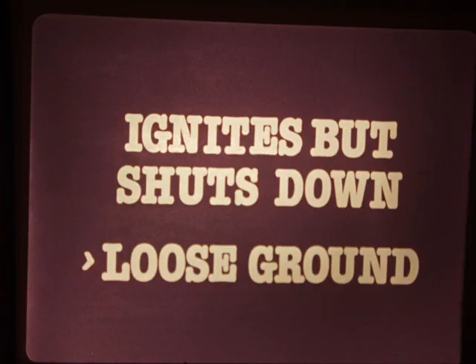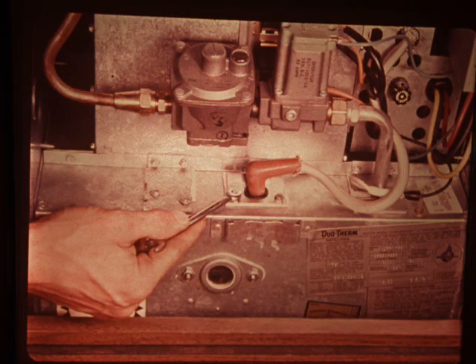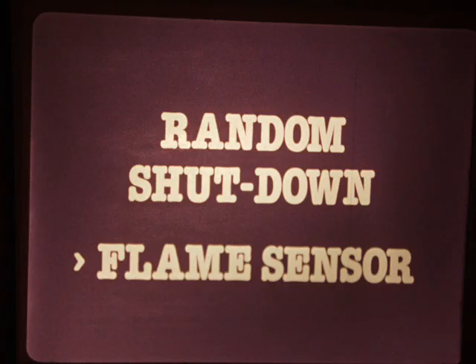If the furnace ignites but shuts down after just a few seconds, first check for a loose furnace ground wire. Secure the green grounding wire to the ground screw near the blower relays. On early furnaces, the wire is grounded in the furnace junction box. Next, check for loose mounting screws on the burner assembly. If the furnace shuts down randomly during the duty cycle, the fault is likely the flame sensor.